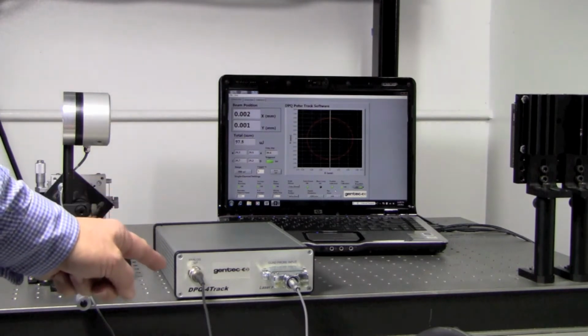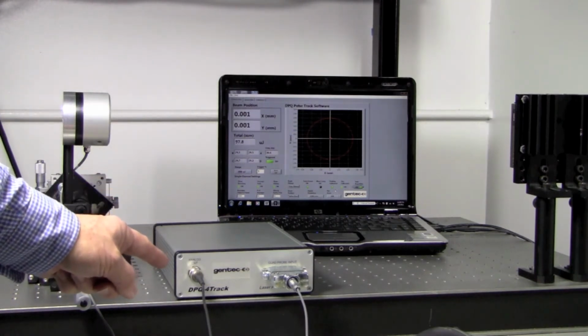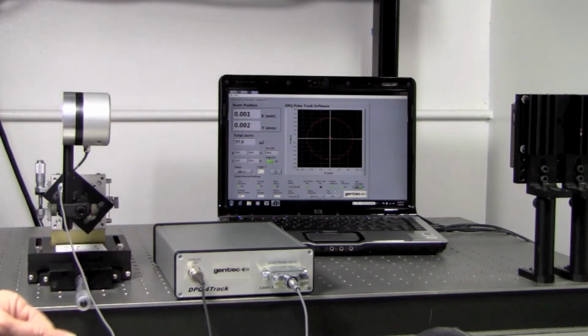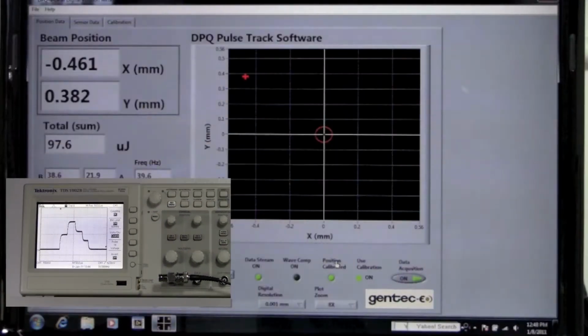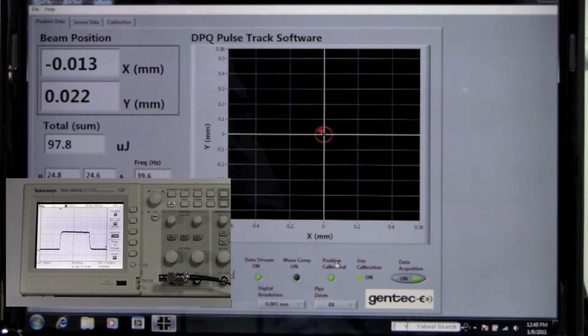The analog output is connected to an oscilloscope, which can be used to view all 4 channels simultaneously. Let's take a closer look at this handy feature. Watch as we adjust the stage to center the laser beam on the quad detector. Note that as the voltage output of the 4 channels become equal, the graphic cursor on the PC screen also heads to the center of the XY axis. This is a great tool when setting up the probe. It can also be used for quick alignment tasks.